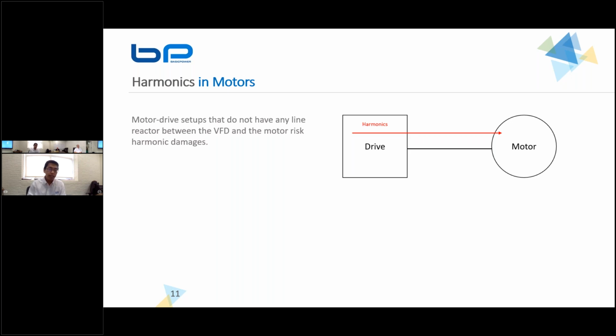Now, this is a key difference between VFD setups and ECMs. ECMs are compact motors. They have drives built within the motor, and the issue with that is, because it's so compact, it's very hard for us to provide any filtration for that exact motor. VFD setups are easier because they're separate from the motor, and we can always add something in between to protect the motor itself.